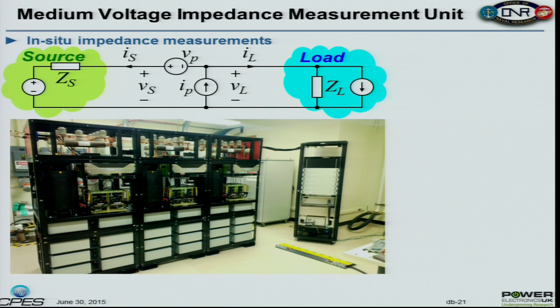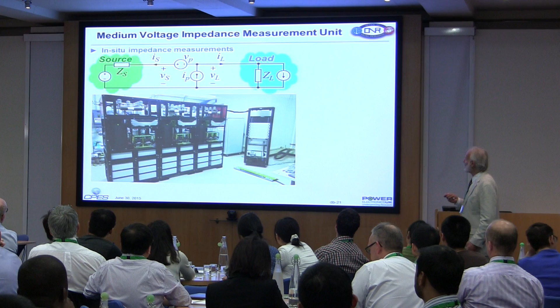The essence is injecting a perturbation into your system. This is a one-line diagram for a three-phase system, injecting either a series voltage or a parallel current, about 1 to 5% perturbation compared to the total power flow from source and load. Then you measure voltages and currents, dividing one by the other, or using matrices, to find impedances.